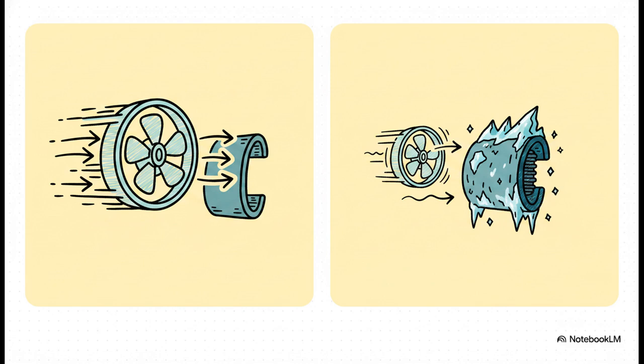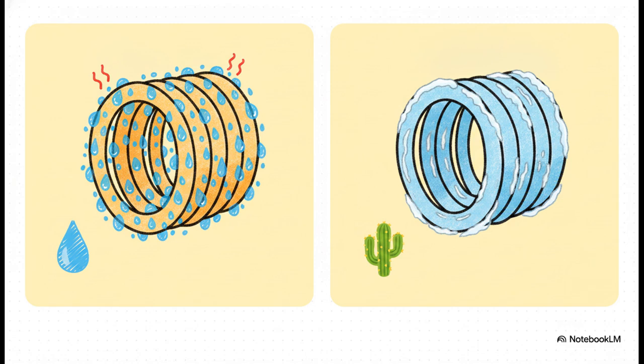On the flip side, if you use a low fan speed, the air moves much slower. This allows the incredibly cold refrigerant to strip away way more heat from fewer air molecules, dropping the coil's temperature down closer to a really chilly 4 to 6 degrees Celsius. The second major variable we have to look at is the latent heat load, which is your humidity. When humidity is high, the coil works incredibly hard to condense that moisture out of the air. This phase change actually releases latent heat directly onto the coil, physically warming the coil's surface. But if you have low humidity, the coil is mostly performing sensible cooling, just lowering the air temperature without condensing much water, which allows that coil to run significantly colder.